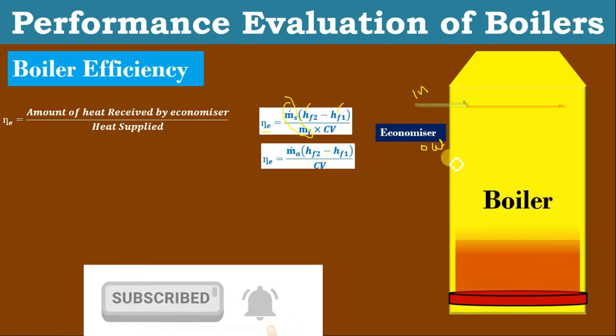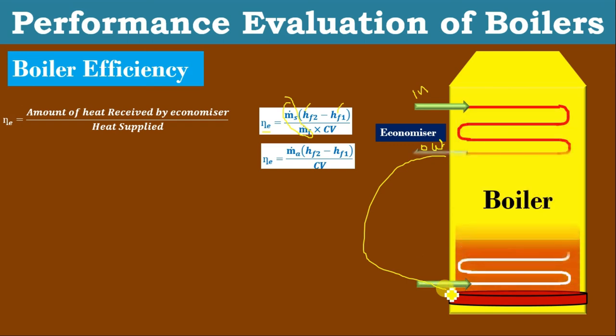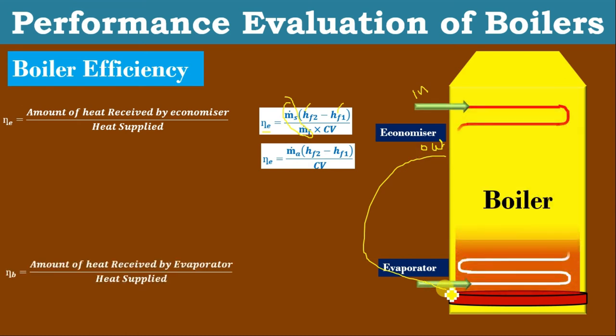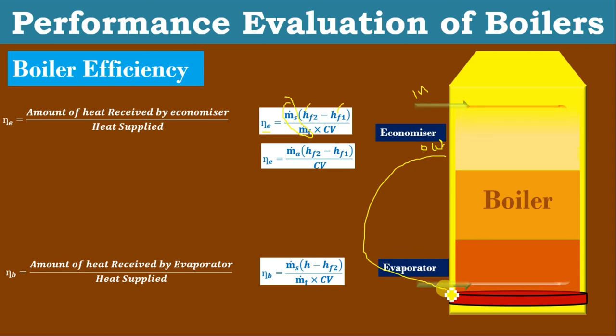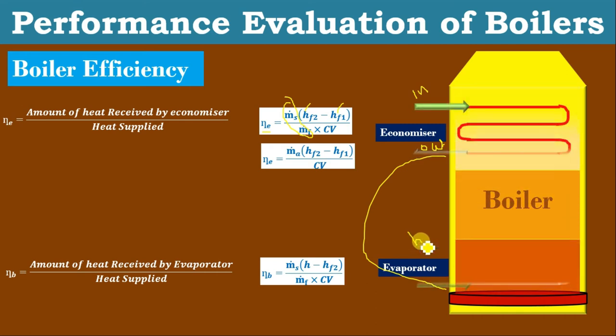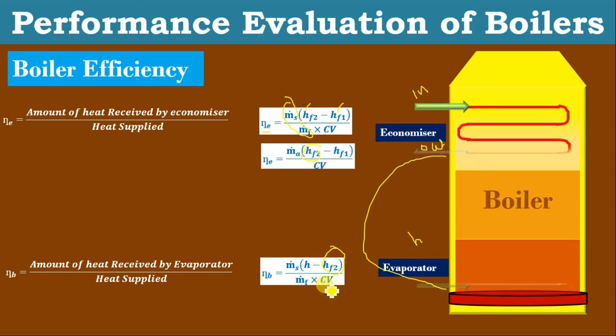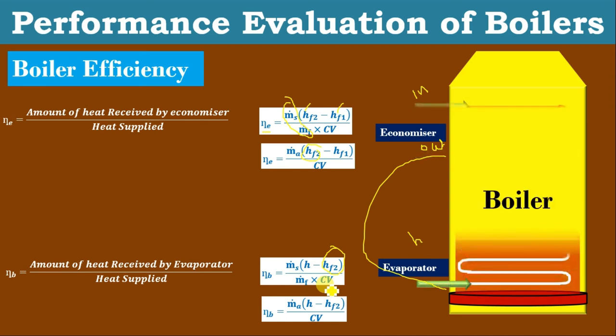Next, after the economizer, the water enters into the evaporator, where it converts water to steam. To find out the evaporator efficiency, again the amount of heat received by the evaporator divided by heat supplied. The efficiency of the evaporator: mass of steam generated × (outlet enthalpy of the evaporator — which may be wet steam, saturated steam, or superheated steam — minus inlet enthalpy of the evaporator, that is the economizer outlet enthalpy Hf2), divided by Mf × Cv. This equation can be written as: M_dot_A × (H − Hf2) / Cv.